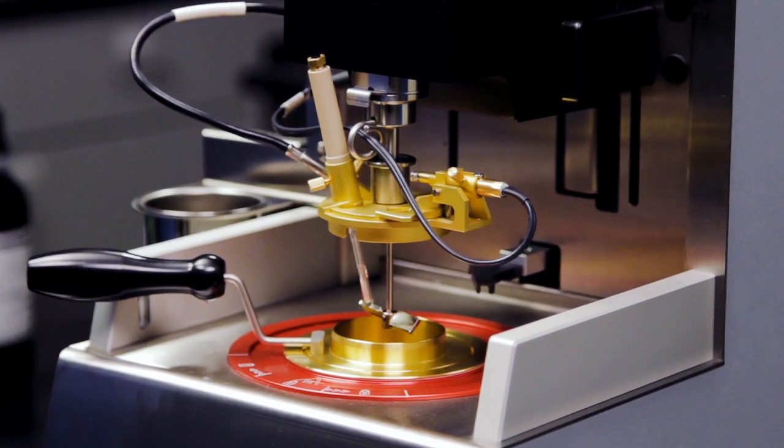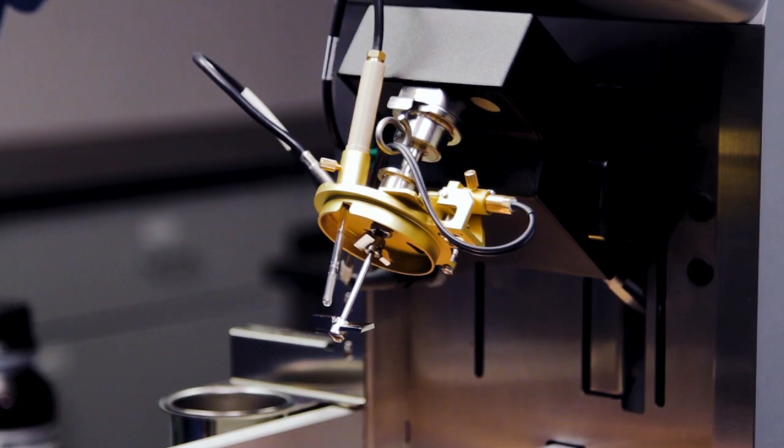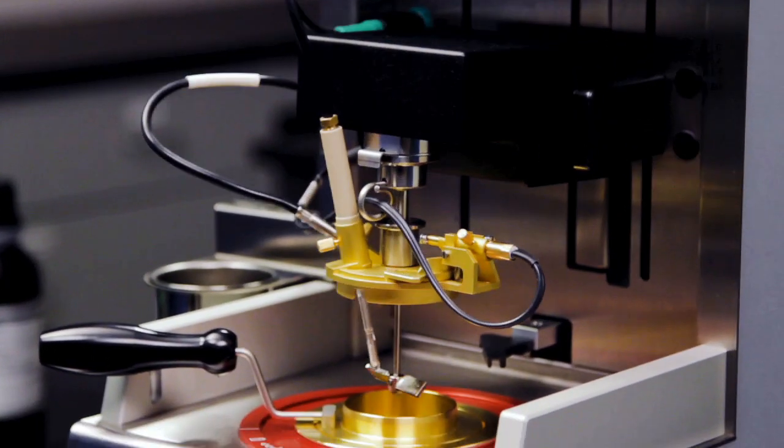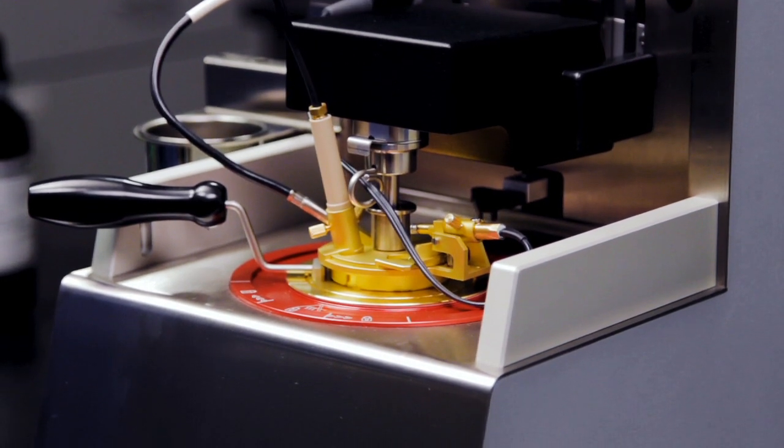OptiFlash offers additional ease of use with an optional automatic lift arm, which means users do not need to install the flashpoint sensor, temperature sensor and test cup cover for each test like with previous generations.